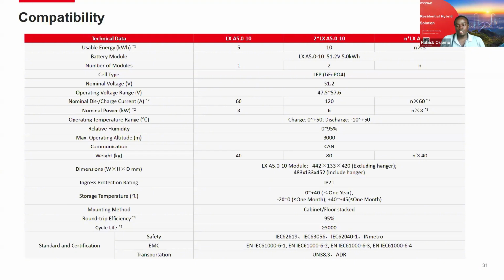Now with the Generation 1, this is a 0.6C. So a 5 kilowatt hour battery can withstand a maximum draw of power or discharge of up to 3 kilowatts maximum. So we scale these up depending on the number of batteries. The Lynx A Generation 1 can do 15, Generation 3 can do 30 pieces to scale it up.